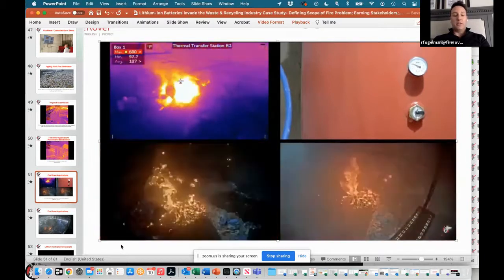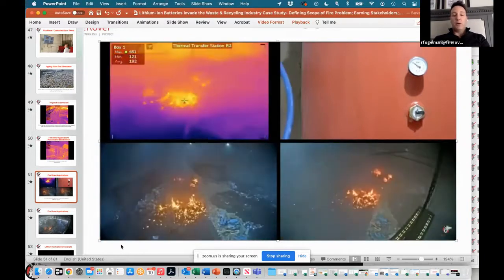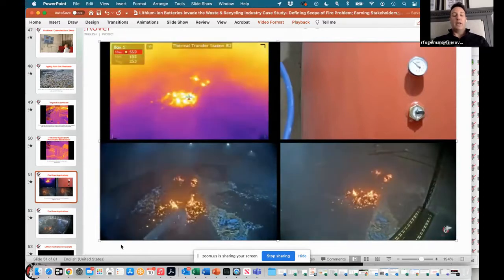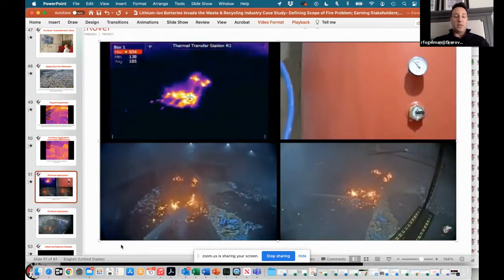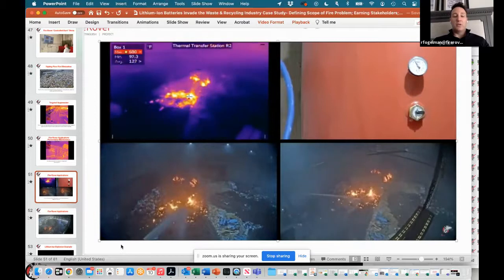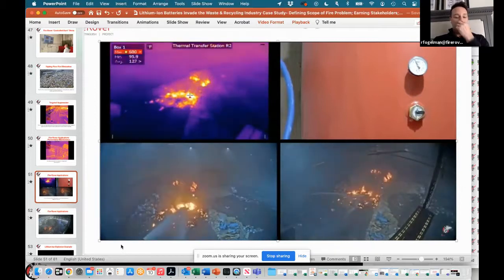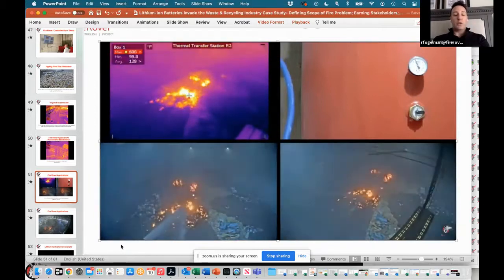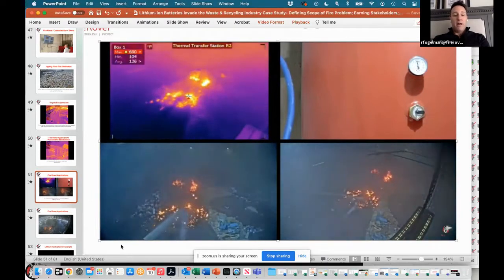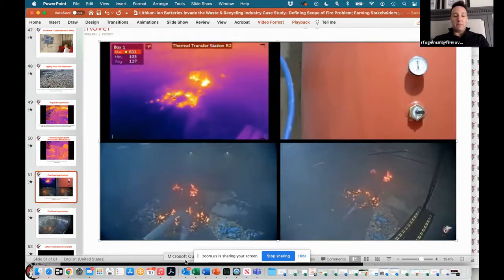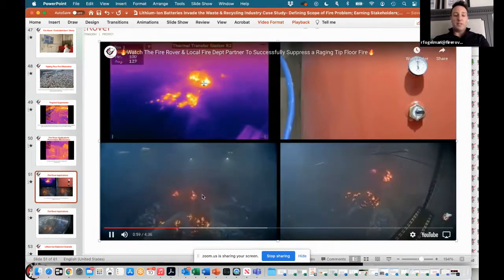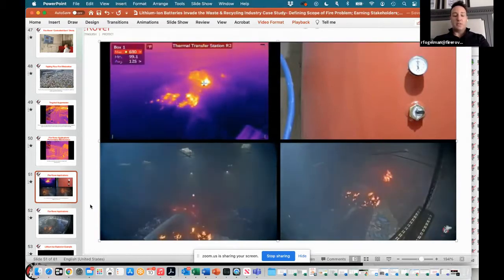What you're supposed to do with a deep-seated fire is pre-wet it and then start layering it away and look towards the fire. As you can see in this situation, it's helpful to know there was no damage here. They were working the next day, so there was no damage at all. What you're going to see here just looks like a mess, but what we're doing, you see that fire extinguisher, not sure why he's there or what he's doing, but you can see the difference between the power of what we're putting out and what they're doing.